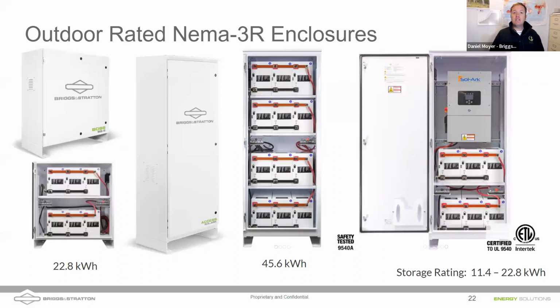What also matters is keeping rain out of your batteries. Our SimpliPhi batteries and Amplify batteries, which you're seeing in these cabinets, are not outdoor rated. The Simplify battery, the larger square one, is outdoor rated. So if you're using Phi or Amplify batteries, we have great cabinets for that, the Boss 12 and Boss 6 cabinets you see on the left. We can even take a Boss 12 cabinet, put an inverter on top and six batteries on the bottom, giving you an outdoor NEMA 3R rated enclosure.